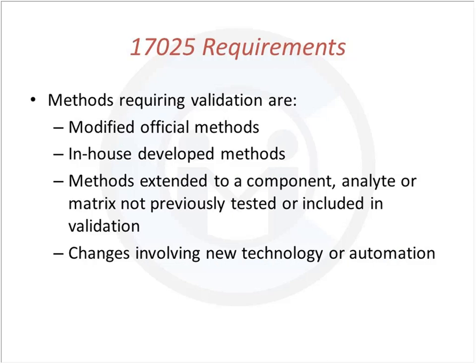Similarly, if you're extending a method to a component or matrix not previously tested or included in the validation study, you have to assess whether the method performs equally well with that new matrix — looking at certain performance parameters that could be impacted, not all of them. For example, for a quantitative method you look at relative recovery; for a qualitative method you look at sensitivity and specificity. Any changes involving new technology or automation also have to be validated. ISO 17025 does have these requirements, though they're not always clearly spelled out.